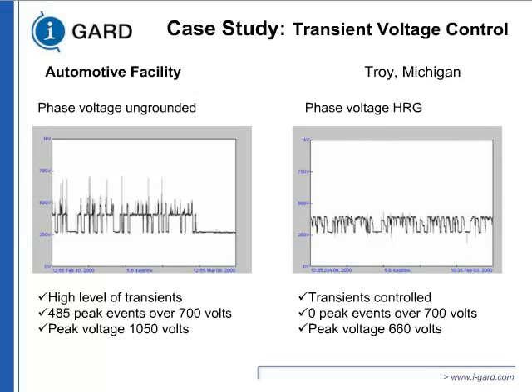The other thing you notice is that peak voltage was, in certain cases, 1050 volts on an ungrounded system. A cable that you have is rated for 600 volts at max, used at 480 volt. At 1000 volts, if you consistently give it such kind of transients, it's going to eventually fail. Now, cable failure was less damaging than motor failure, because cable failure we could repair. Motor failure we could not repair without replacing. So, high resistance grounding relieved that problem for us.